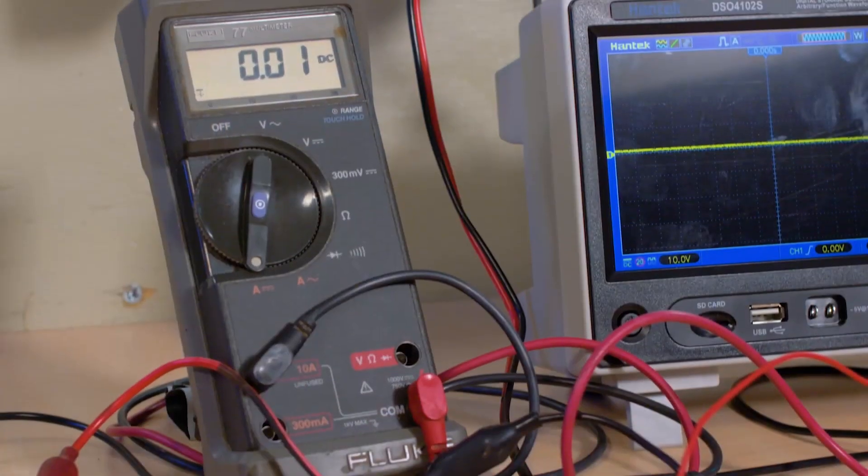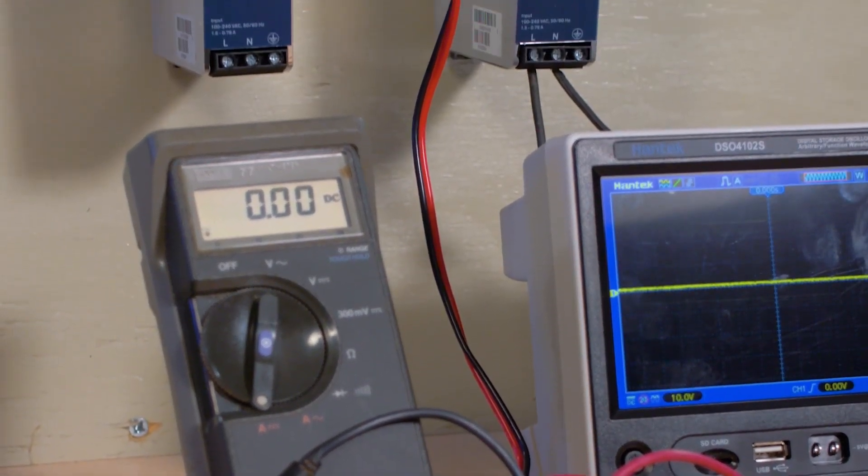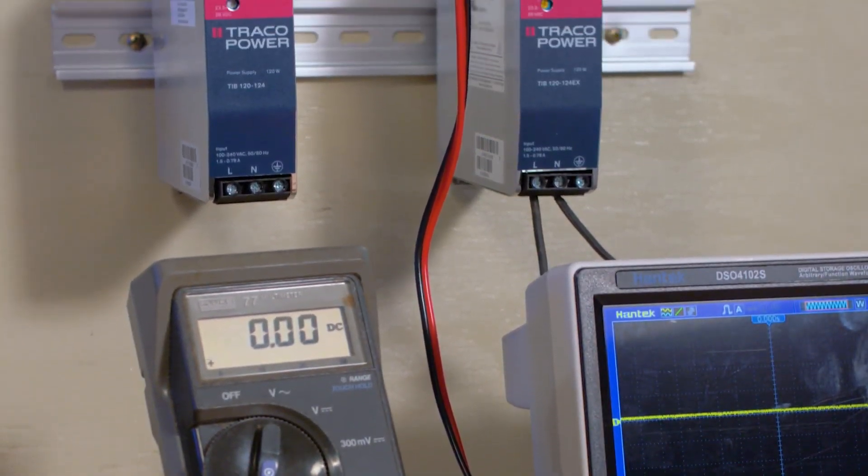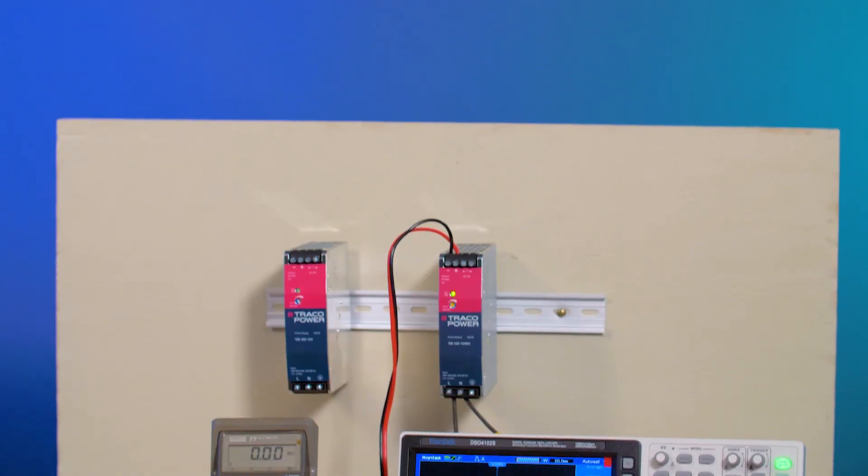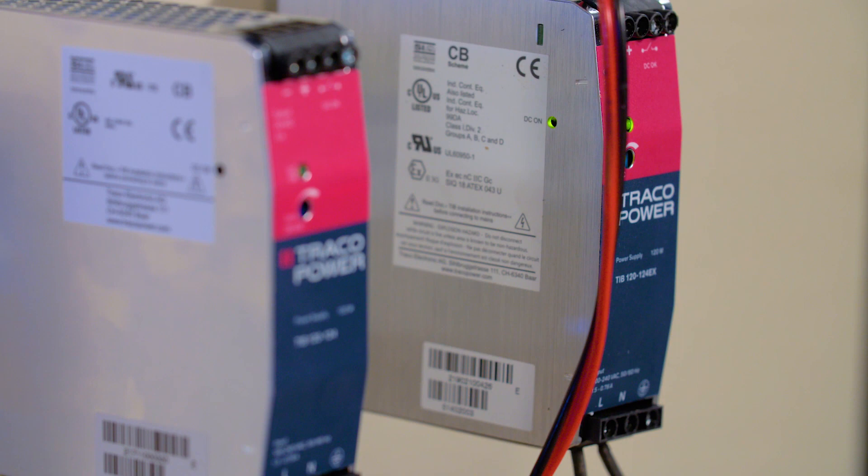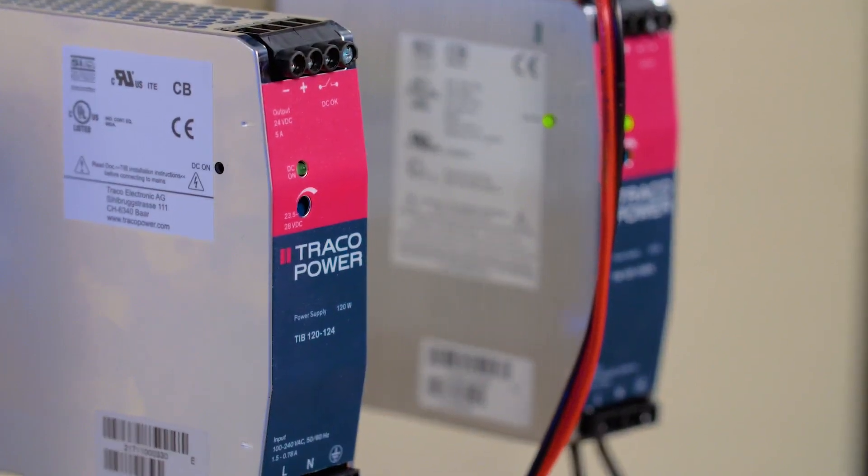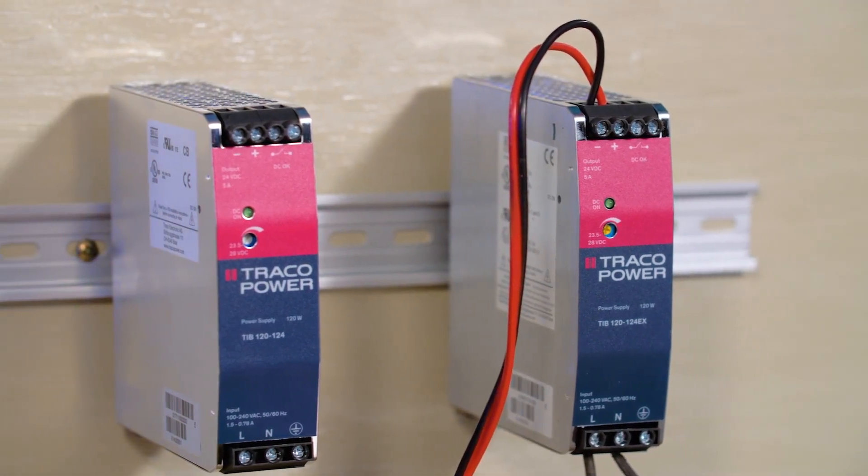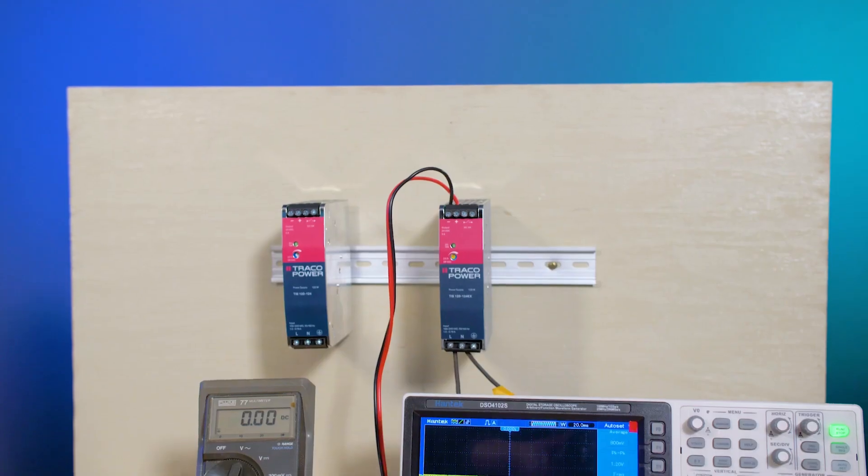Traco says they typically operate in the 90 to 95 percent efficiency range, depending on the output voltage, and support a full load temperature range of minus 40 to plus 60 degrees centigrade with no derating and up to plus 70 centigrade with only a 20 percent derating. What that means is they can run cool though they are strictly cooled by convection.